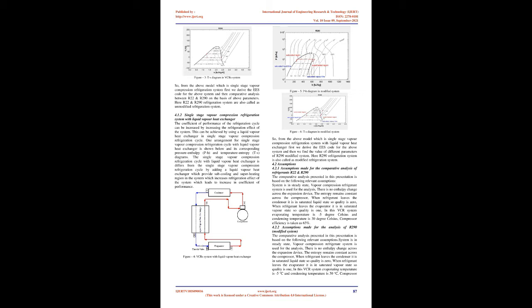Hence there is not much difference in the physical properties of R22 and R290, and R290 can be used as a substitute of R22 due to its excellent thermophysical properties. The thermophysical properties of a refrigerant determine the energy performance of the refrigeration system. The above table shows the thermophysical properties of refrigerants R22 and R290 at an evaporating temperature of 10 degrees C and a condensing temperature of 45 degrees C.